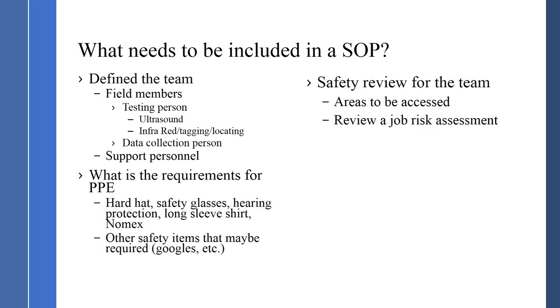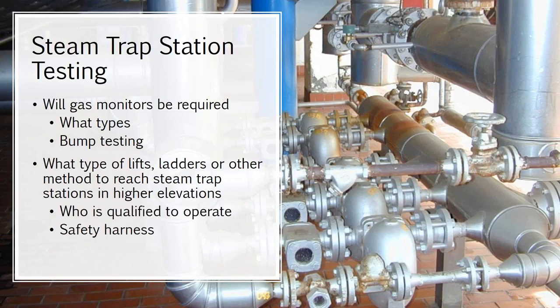For steam trap station testing, we also address other devices that might be required: gas monitoring, such as H2S monitors, and bump testing those monitors. We cover types of lifts, ladders, and other methods to reach steam trap stations at higher elevations. The SOP specifies who is qualified to operate lift ladders, what type of safety harness is required, and whether the plant will provide the safety harness — all part of getting prepped for the steam trap assessment. Equipment needs include flashlights, which must be intrinsically safe since many locations require it. The SOP addresses which ultrasonic unit is being used — a UE 9000, 10,000, or 15,000 — when it was last calibrated, and whether calibration documentation is available.